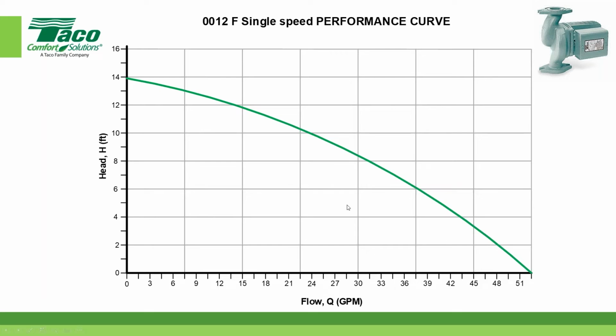Okay, so it's based on very, very accurate information under laboratory test bench conditions. So I will say this, the circulator performance curve will be the most accurate representation of what that circulator can do or will do within a system. That's why, when people call me and they say, Rick, can you just cross-reference a pump for me? Well, I want to know what it needs to do, because brands X, Y, and Z don't always match up. They don't always look the same. They don't always have the same angles or pitches, or whether it's a steep curve or a flat curve. It might meet somewhere within that, but not be an appropriate pick. So I always want to know what the operating or the duty point is, and then I can better help somebody size the circulator. But you need to have your arms around this stuff.